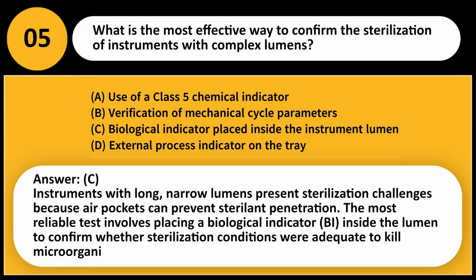Answer, C. Instruments with long, narrow lumens present sterilization challenges because air pockets can prevent sterilant penetration. The most reliable test involves placing a biological indicator, BI, inside the lumen to confirm whether sterilization conditions were adequate to kill microorganisms.